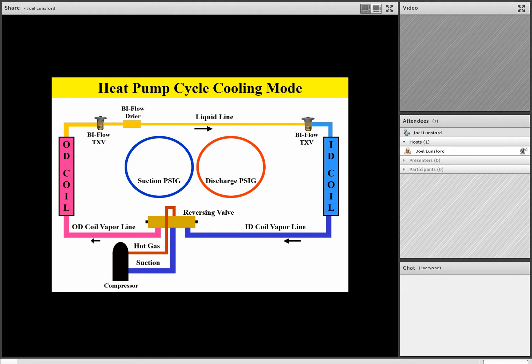Now also, as you take a look at those gauges, you'll notice that they have a white background. If you have a white background on any of our service calls throughout the rest of the day, you'll automatically know it's an R22 call. If it has a rose-colored or pink background, you'll know that those gauges are indicating a 410A service call. So, starting at the compressor, we see that we have a hot gas line from the compressor going to a single line on the reversing valve.